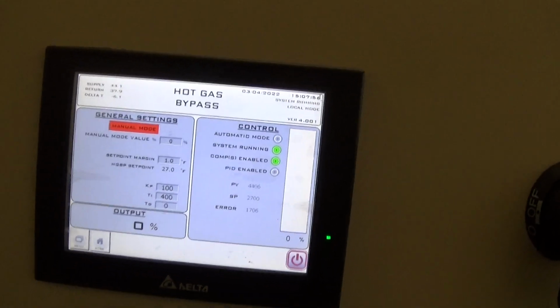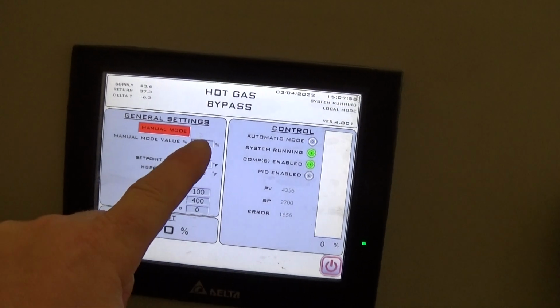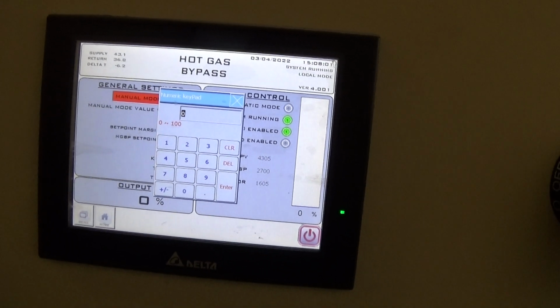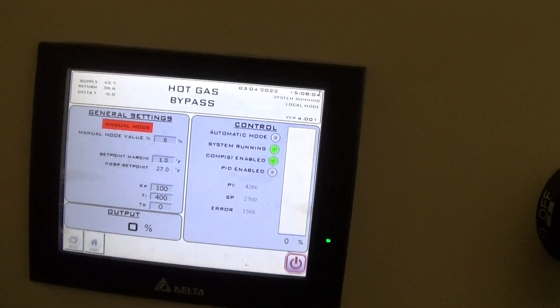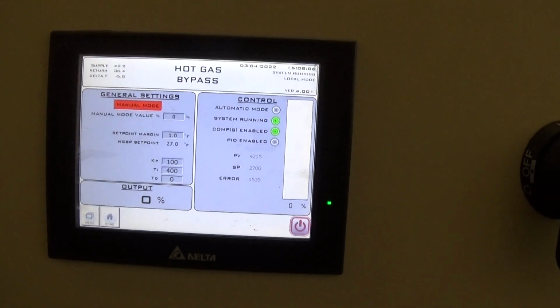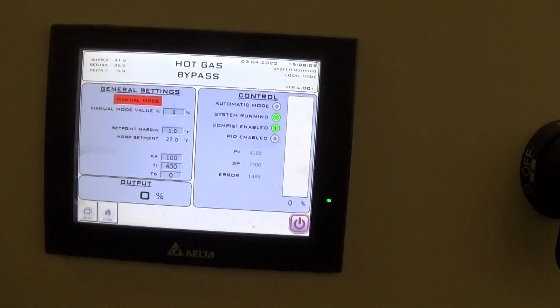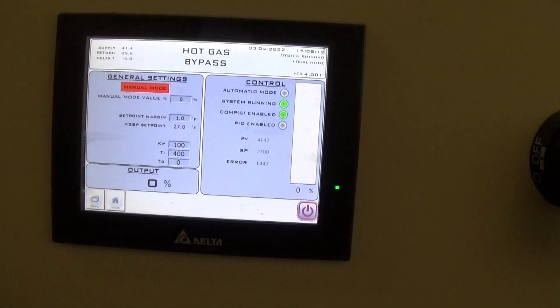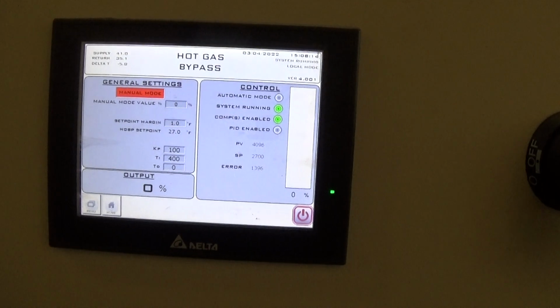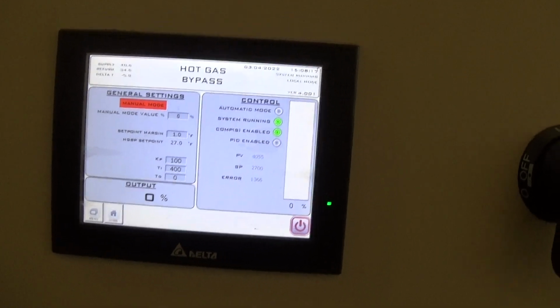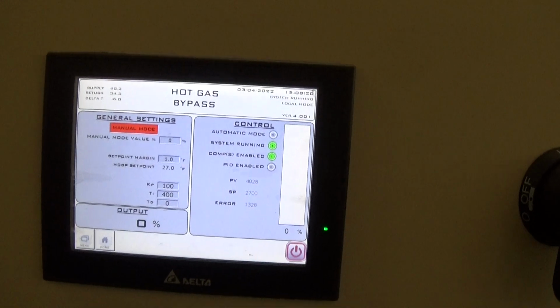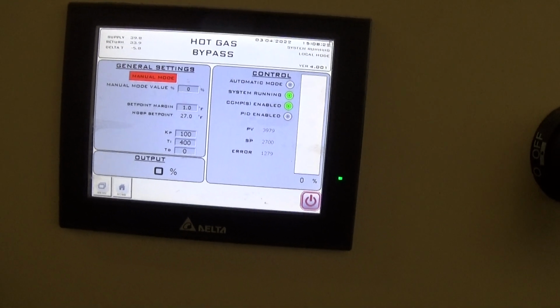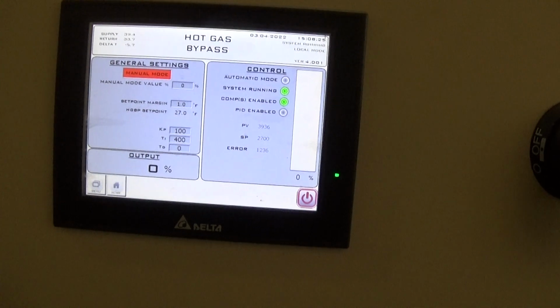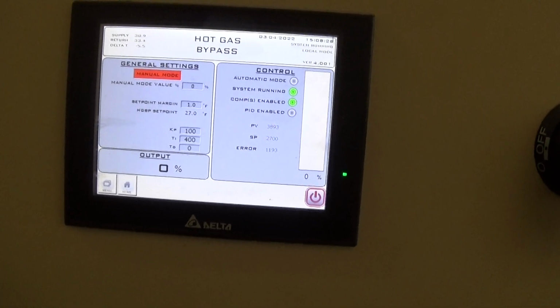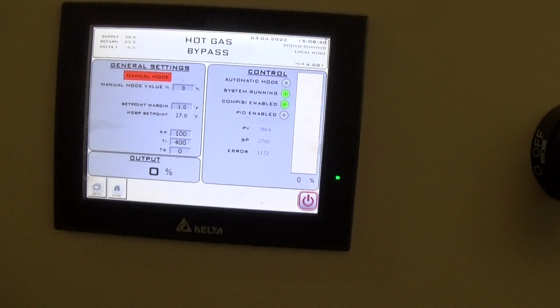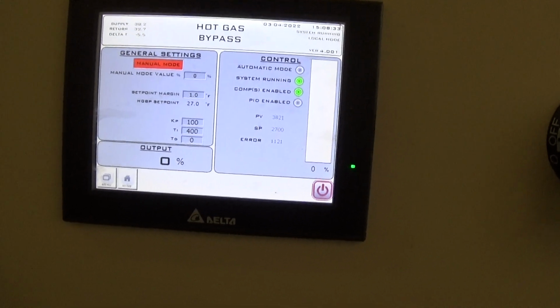Hot gas bypass, we have it in manual mode. We have it basically at the 0 number right here. We could go in and check and change that. We firmly believe the hot gas bypass is ideal for warmer running temperatures in a non-batch cooling environment. We rarely, if ever, see it really needed for a brewery glycol chiller. So we're going to ship the hot gas bypass at 0. If we kick it up, basically the compressor would never turn off. We'll be constantly running and trying to adjust to maintain a tight temperature tolerance, which you really don't need for this application.